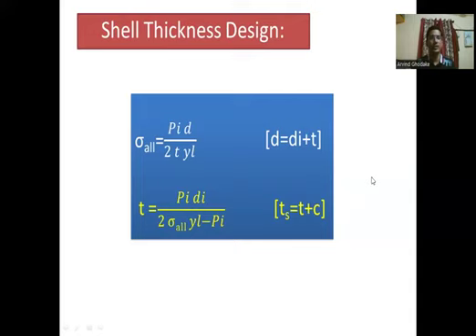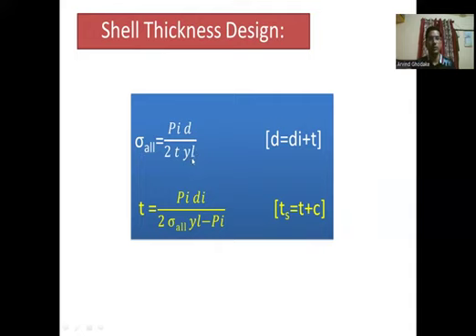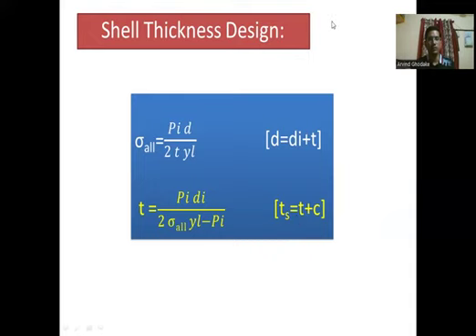The standard formula for shell thickness design is: T = (PI × DI) / (2 × sigma_allowable × eta_L − PI), where sigma allowable is the allowable stress and eta_L is the joint efficiency. The outer diameter D = DI + T, and the actual shell thickness TS = T + C, where C is the corrosion allowance.